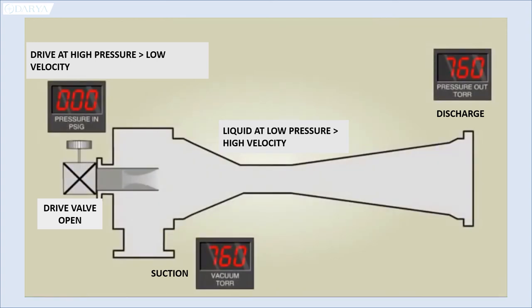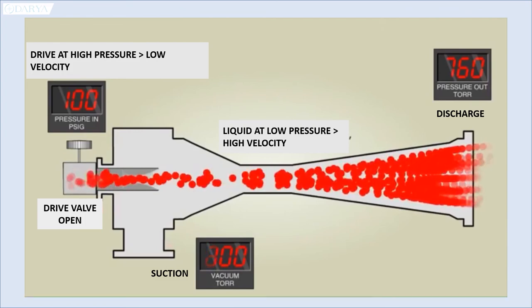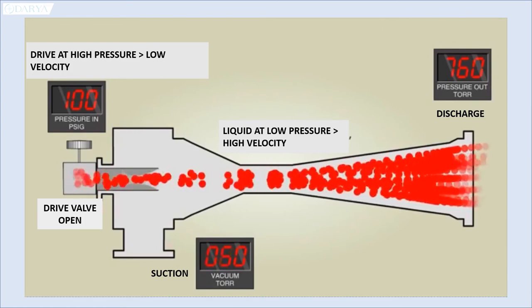Suction valve is kept closed in starting, discharge and drive valves are kept open. Drive liquid enters at high pressure or low velocity which when expands in diffuser, the velocity is increased and pressure is reduced which creates suction.